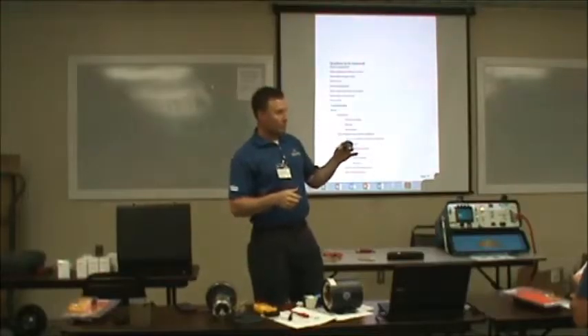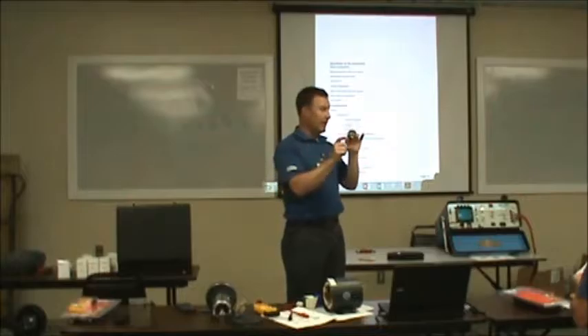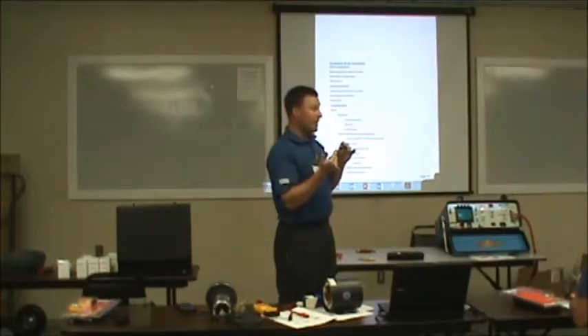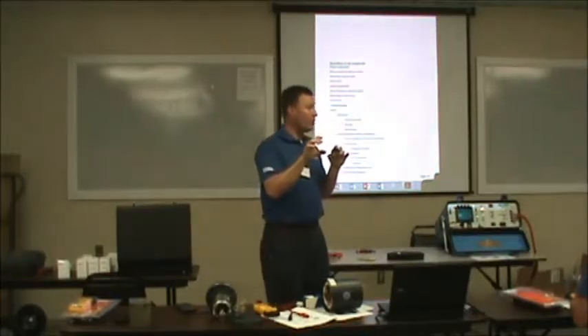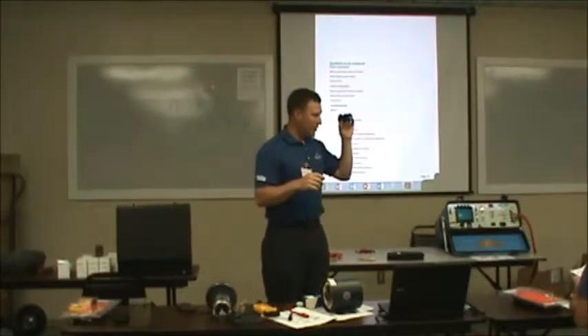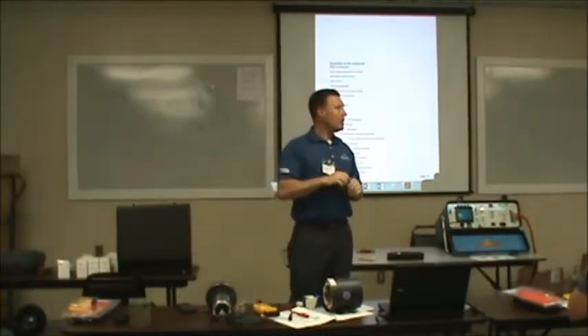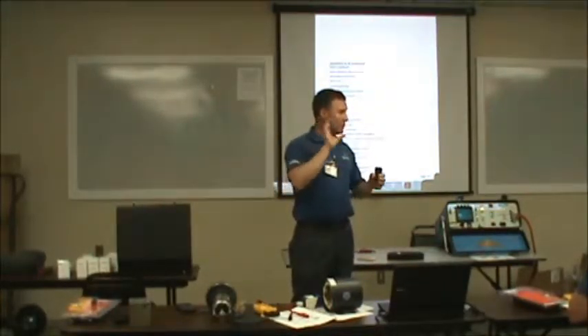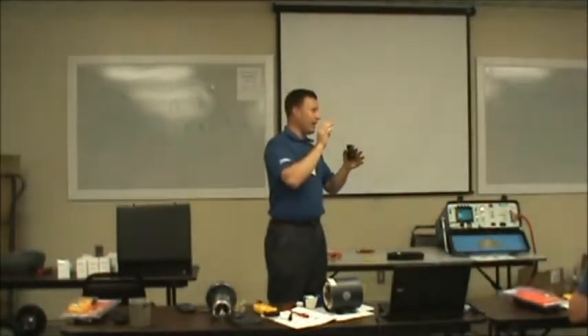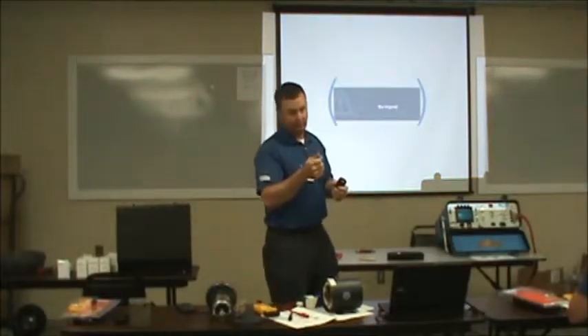So most of the time when this blows, it's staying in circuit. That can be caused by the pump station, by the starter relay, or your pump's clogged and not spinning, so your readings are not right on your starter relay. It can be the motor too. If it doesn't get up to speed quick, say it's dragging a little or turns hard, then it will. Those starter relays use a voltage to amp ratio, and I'm not real familiar with them. The way I test them is I pull one out and put another in.